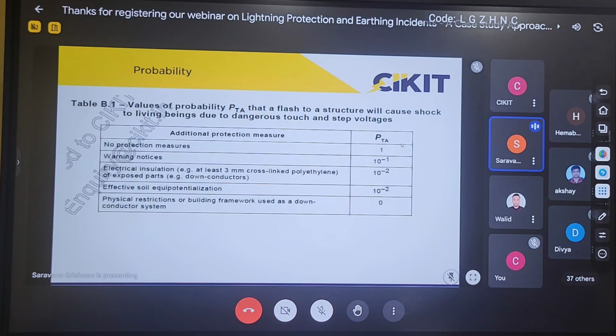So the standard has provided different methodologies and prevention measures for reducing injury to human beings due to step and touch voltages. The first one is a warning notice. Power panels provide warnings like danger 11 kilovolt, danger 22 kilovolt, danger 110 kV line. Similarly, I can provide a warning notice on the down conductor, like danger, don't touch, it is a lightning conductor. If I make contact, touch potential will come into the picture. If I don't make any contact, the touch voltage can be avoided. So one prevention measure is having a warning notice. Even with a warning notice, accidental contact can still happen.